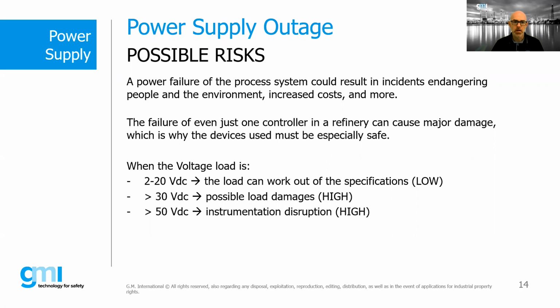But what are the dangerous conditions for a power supply system? Well, mainly there are two dangerous fault conditions. The first one is an undefined load voltage in a range between 2 and 20 volts. This must be considered a dangerous failure of our power supply. This is because an incorrectly powered load works, or can work, out of specification. And this leads to a reduction in load performance that can cause a premature instrument failure.